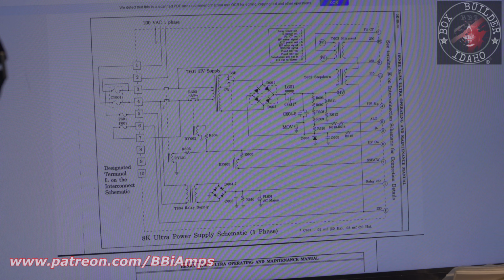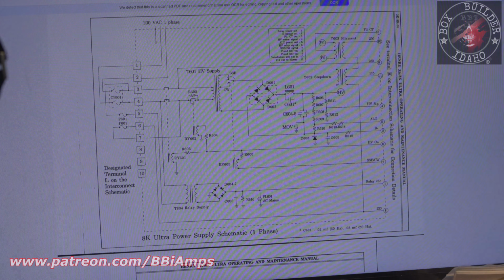Right now we're focused on this. This is the single contactor that sits by itself. Very low current is what goes through here. That's what we're discussing here. And he had this wired upside down, so basically backwards. He had this lead wired to this lead and this lead wired to this lead, but in reverse.